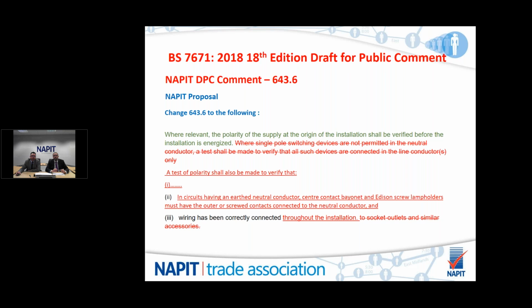So our proposal will be to keep the first section, polarity of the supply at the origin, which is important. The part on single pole devices not being permitted in the neutral, we feel that's not necessary, it's not a requirement, shouldn't be in there, shouldn't even be used, so we've taken that out. The test of polarity should also be made to verify. We're proposing putting that part back in, but modifying the wording so it says shall also be made, which implies that you will test the polarity at the origin of the supply, and also you will test to make sure and verify that indent 1 stays as normal.